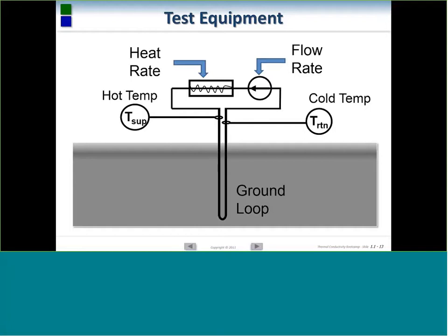But all the studies that I've read up and all the dissertations that I've read over the last several years show very, very marginal increase in accuracy over the heat injection method. It's generally less than like 1 or 2% difference between a delta T method, where they're actually keeping a constant delta T on the heat injection.